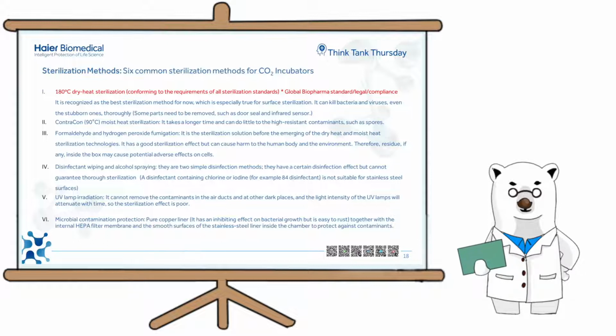Microorganisms which survive the UV decontamination process will potentially have the opportunity to form monocultures and increase their likelihood to reach quorum. This is unless UV sterilization is combined with other methods of incubator decontamination, such as a tear down and wash off of all surfaces, a dispersed chemical treatment, or an effective high heat cycle.